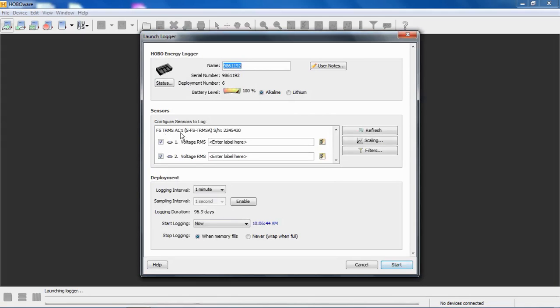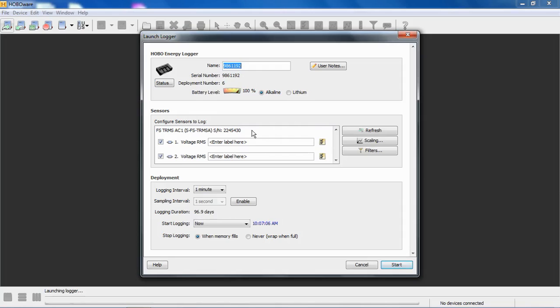Notice we have two channels in each TRMS module. The logger will support installation of up to three of these through the bus on the top of the logger. Here's the serial number of that module. Note that when you have multiple modules installed in the energy logger, they are aligned in this sensors-to-log area in hierarchical serial number order, meaning the lowest serial numbers at the top, moving forward up to the highest.